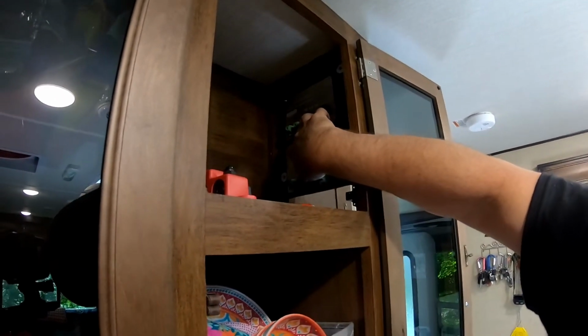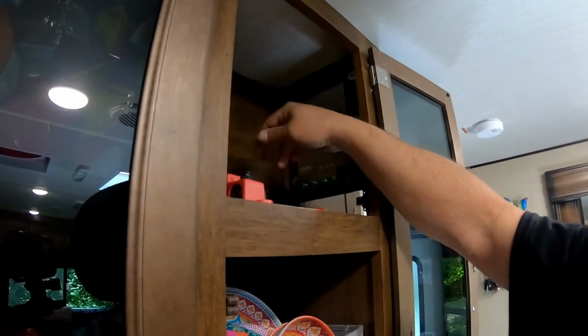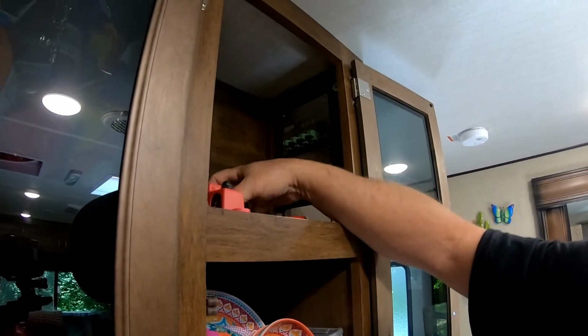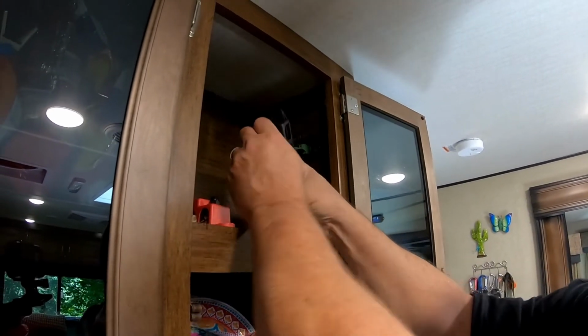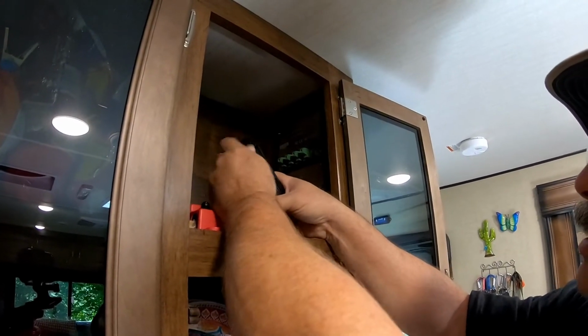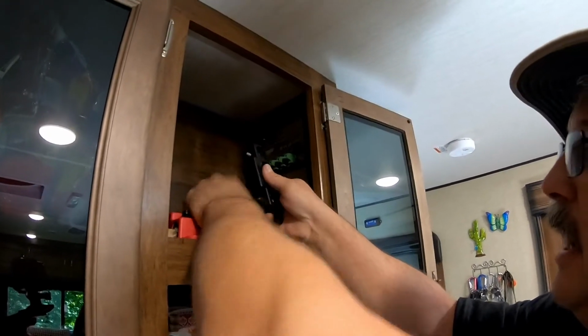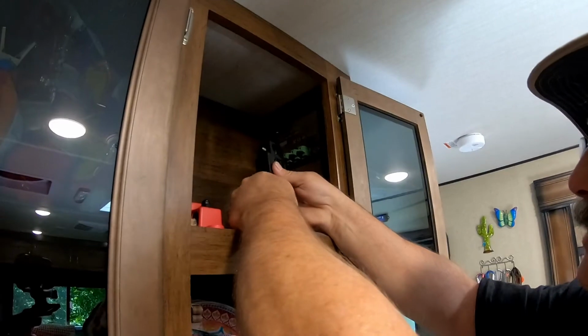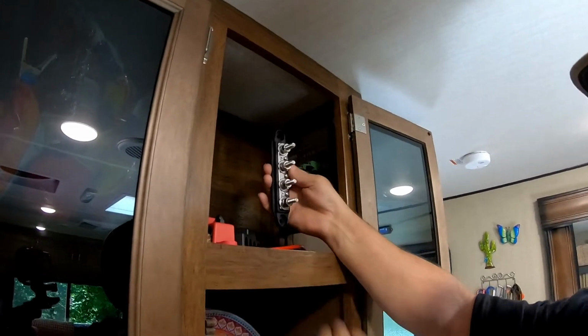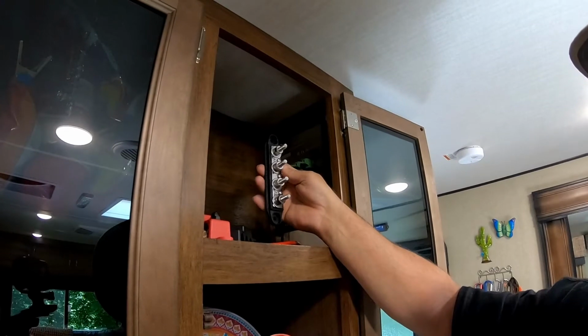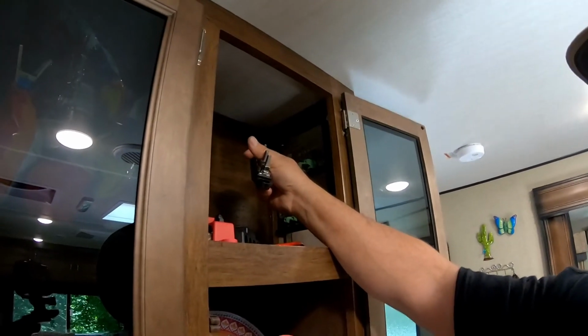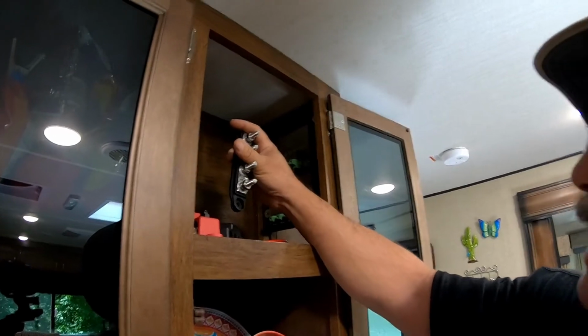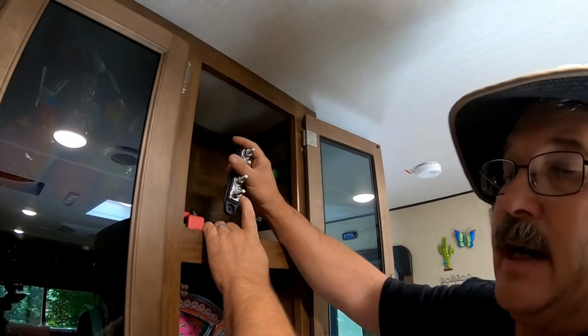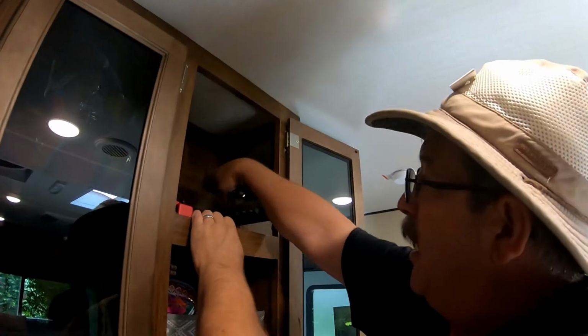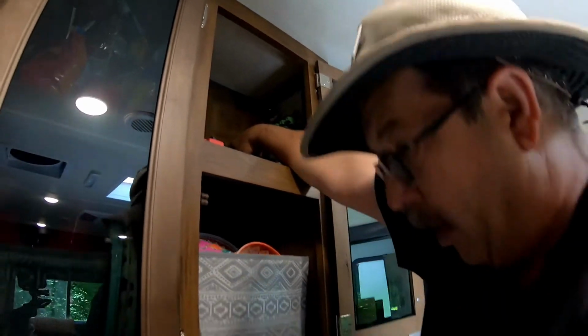On the other side I have my battery. Coming off the battery side, I'll run the negative straight to this terminal block. I bought these terminal blocks to avoid running multiple wires back to my batteries—nice heavy-duty terminal block. I'll mount it somewhere in here and run the negatives to it, then run a 6-gauge wire from this cabinet out through the back, behind the hutch, down to the bottom, and all the way to the batteries.